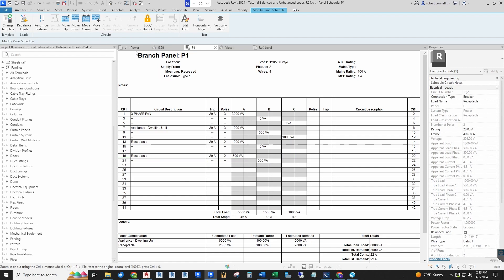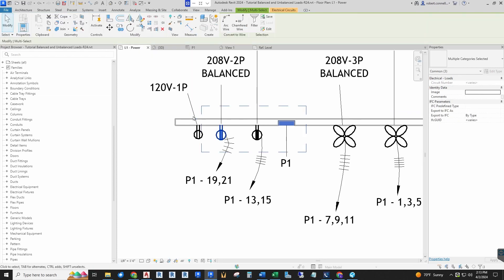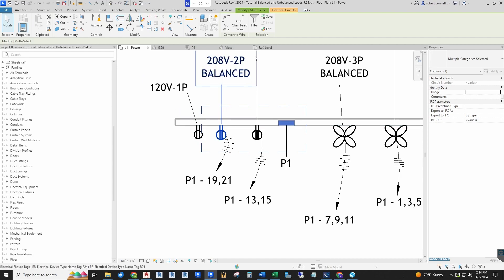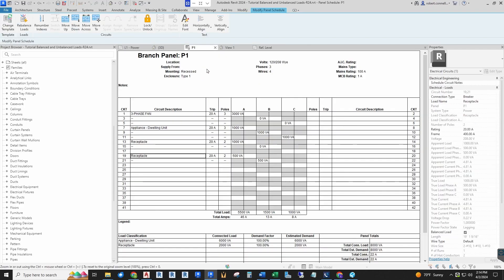And then of course, single pole single phase, there's nothing wrong with those. It's just one pole, one phase anyway. So just remember, 208 single phase is represented with two pole in Revit. You have to get balanced loads for these to be divided. So if you ever have that problem, open that editor, check out that electrical connector, and make sure that it's balanced.